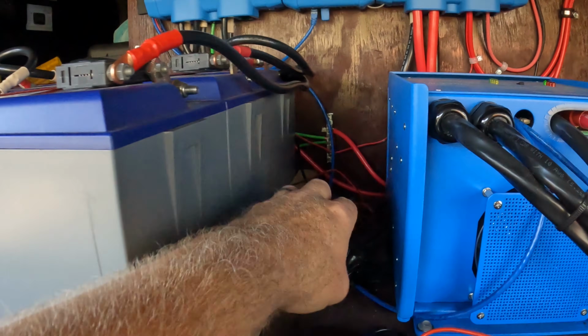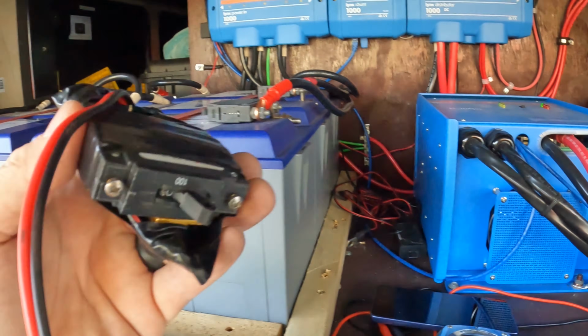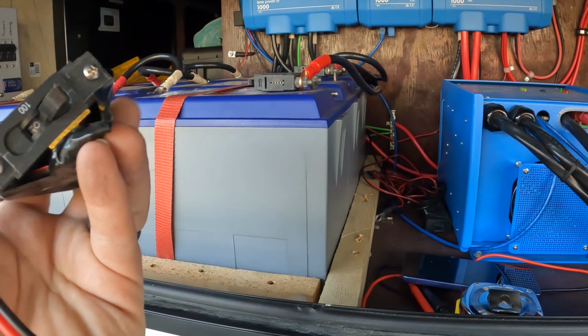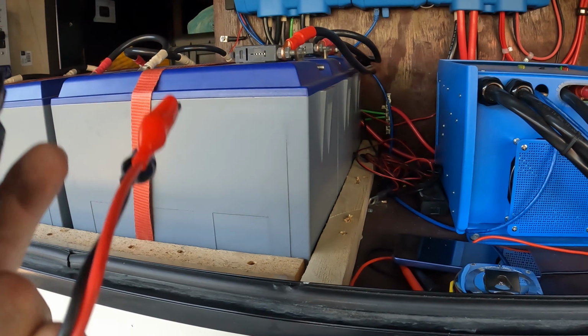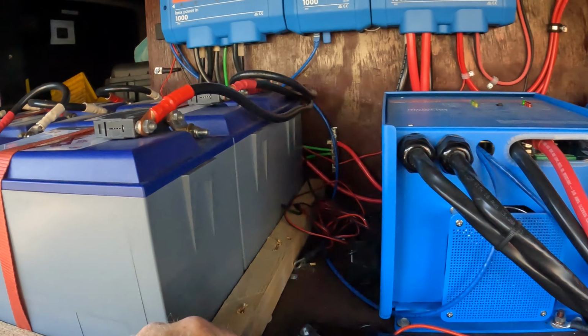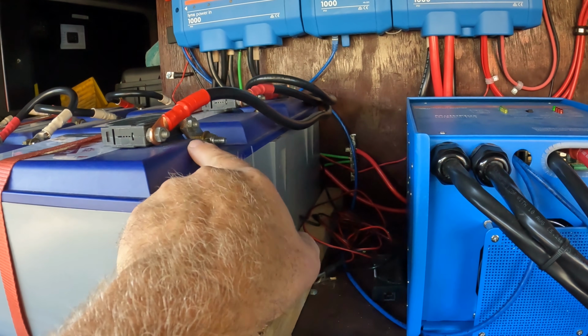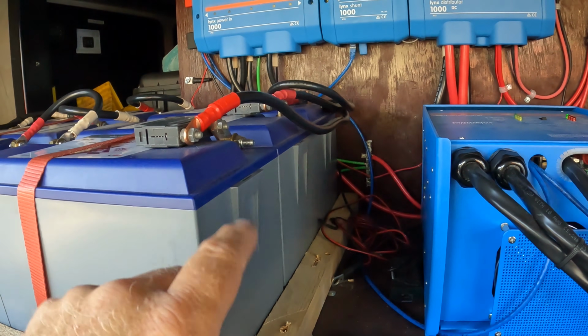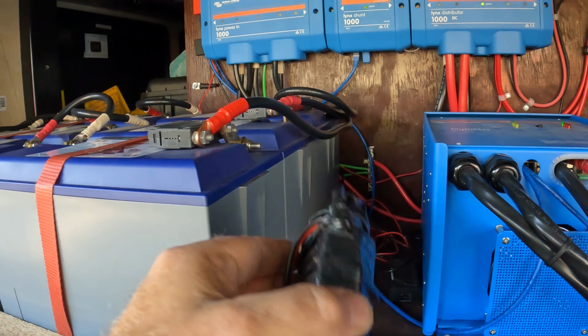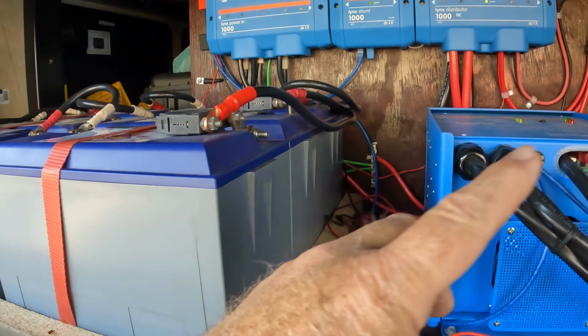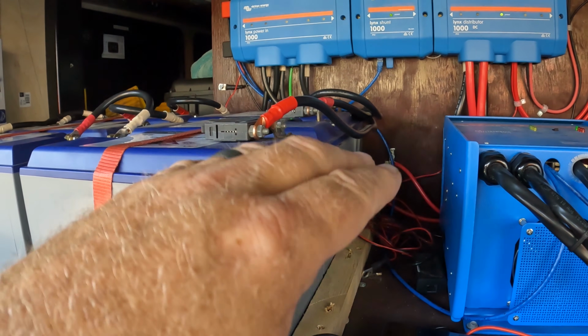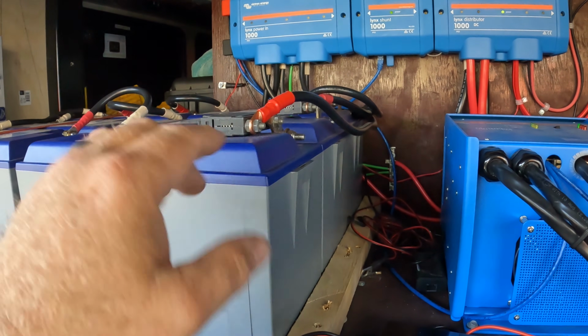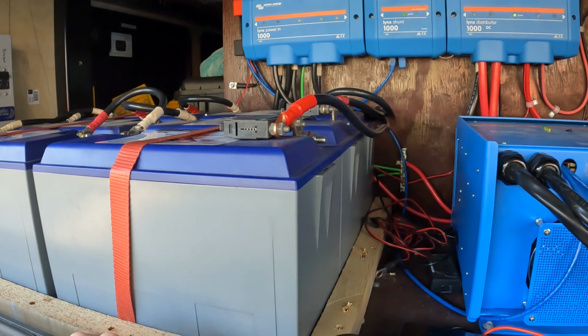So we had to make a breaker with a resistor inside it, wired in with a couple alligator clips. We put that across the breaker terminals on the battery and turn just this on, and it will pre-charge slowly into the inverters, ramp them up and fill them. When the lights start to come on, you can turn all the breakers on and everybody's happy.